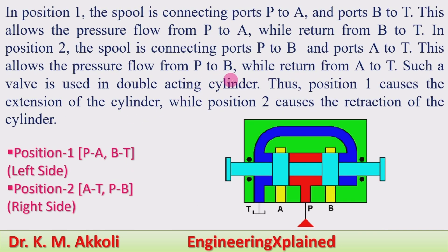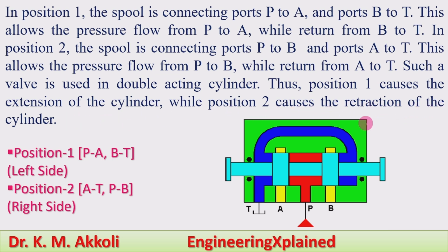In position one, the spool connects port P to A and port B to T. This allows pressure flow from P to A while the return is from B to T. In position two, the spool connects P to B and port A to T. This allows pressure flow from P to B while the return goes from actuator to tank. Position one causes extension of the cylinder; position two causes retraction.